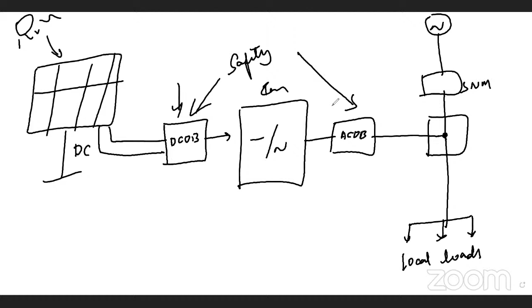Now, in the next slides, we will see the major components involved in these boxes and how they provide the safety. Primarily, the components inside the DCDB are fuse, diode, MCB, and SPD. SPD is the surge protection device. So these are the four main components. Fuse is the first line of safety, MCB is the second line of safety, SPD is the third line of safety, and the diode provides the fourth line of safety. To block the reverse flow of current from the inverter to the panel, a reverse blocking diode is employed.